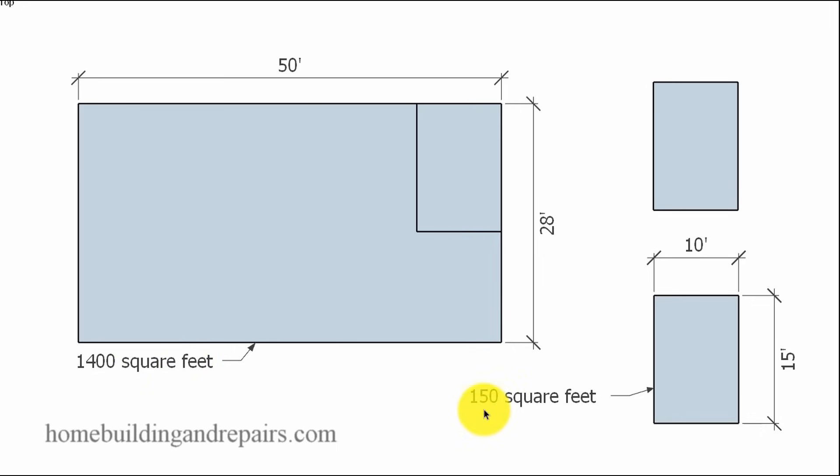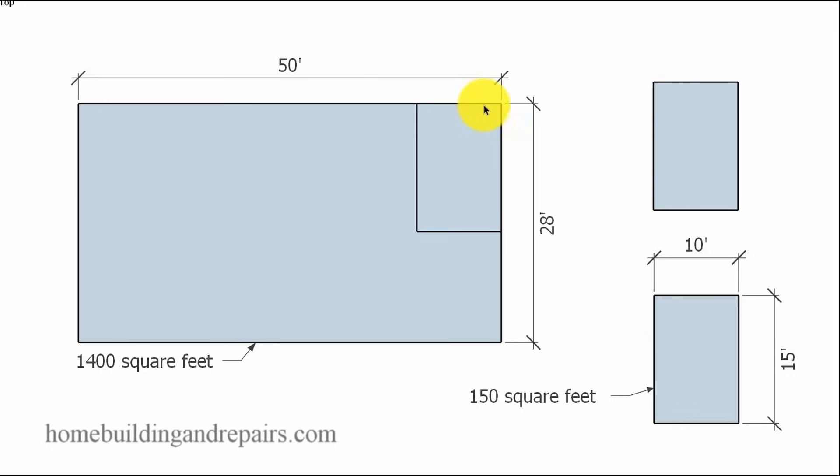Now, for every 150 square feet, which would basically be for every 10 foot by 15 foot of this particular floor area or crawl space area, we will need one 12 inch by 12 inch or one foot by one foot screened vent.